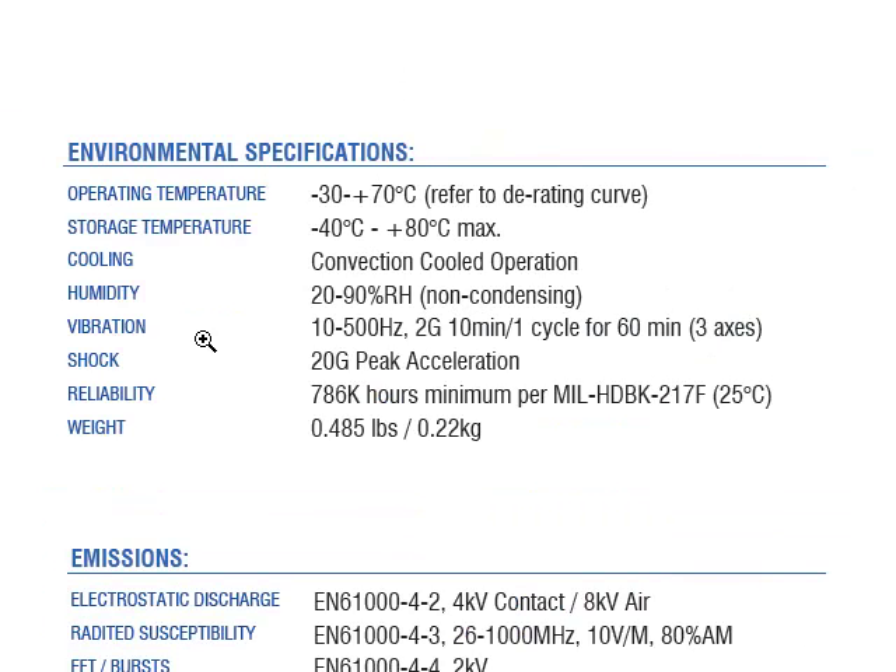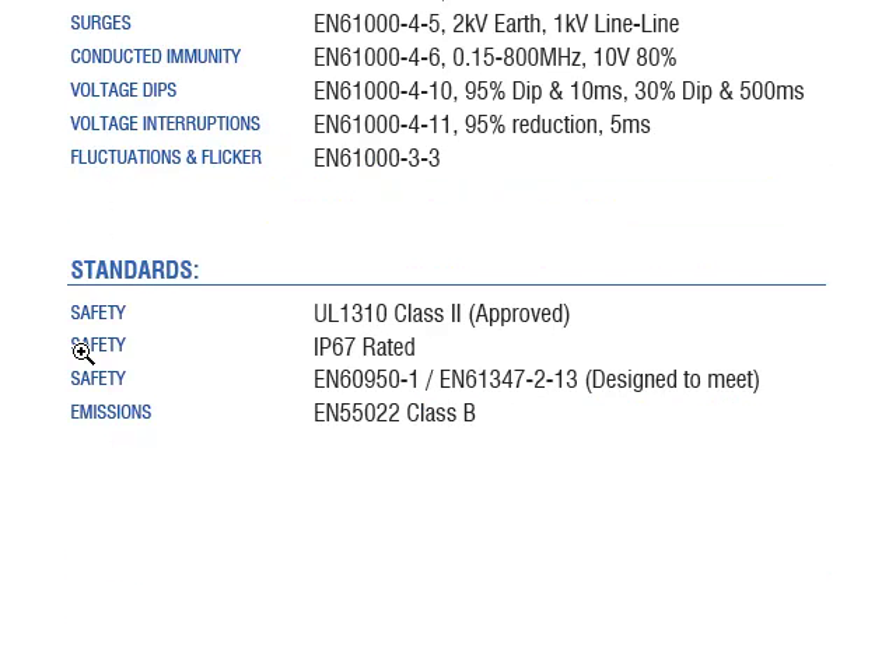The supplies are rated for a negative 30 to plus 70 degrees C operating temperature with some derating. They offer convection-cooled operation and extremely high reliability of 786,000 hours. The products have been safety approved for UL1310 Class II and are IP67 rated, which is ideal for outdoor lighting applications.